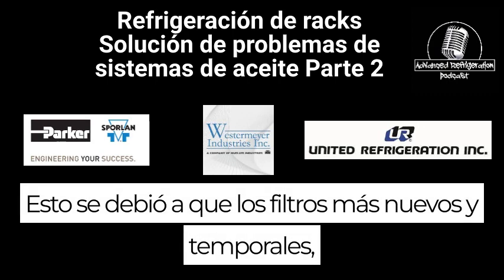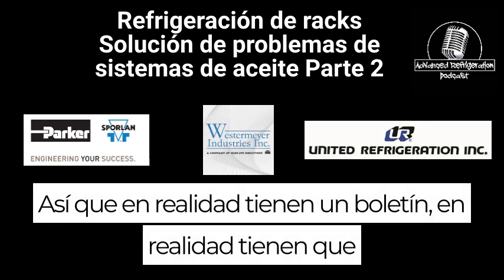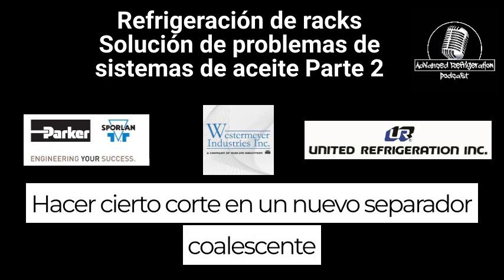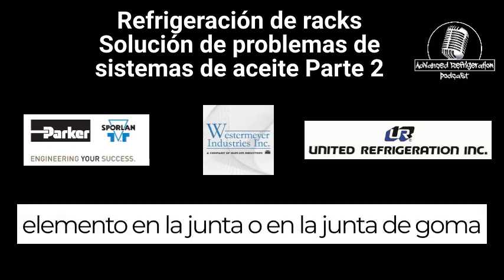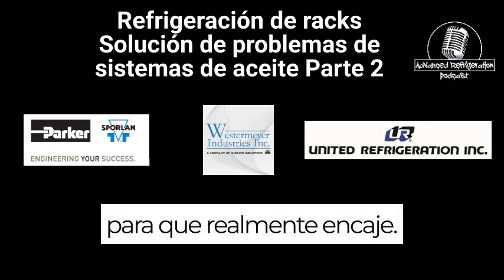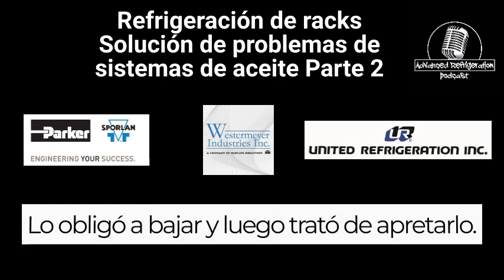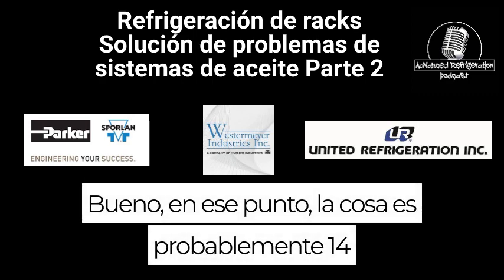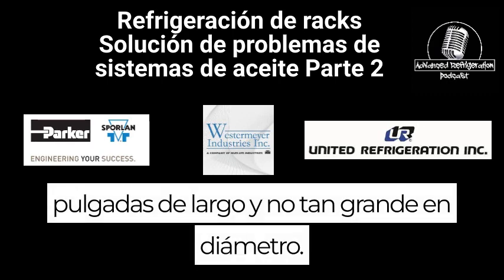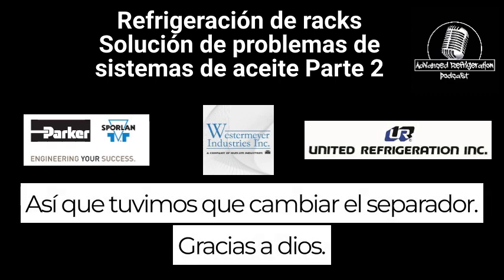This was because the newer Temprite filters don't account for that older style. So they actually have a bulletin. You actually have to make a certain cut in a brand new separator coalescing element, in the rubber gasket, in order to make it fit. So just be mindful of that so you don't force it down, because that's what this guy did. He forced it down and then tried to tighten it down, and he ended up breaking it off. At that point, the thing's probably 14 inches long and not that big in diameter, so there's no way you're going to set a welder down there to fix it. So we had to change the separator.